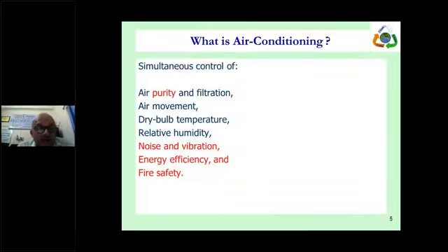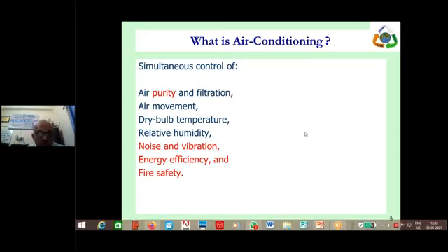Let's start with the definition. What is air conditioning? Air conditioning now often is taken as if just to maintain temperature. Mostly people are talking of only temperature, but the actual definition of air conditioning is that it is a simultaneous control of air purity and filtration. Purity means maintaining the CO2 level, oxygen level and all that. And filtration means particle size. So that is done with filters. Air movement means how much draft you are getting at the user end. How much draft. If it is more, then also it puts you uncomfortable.